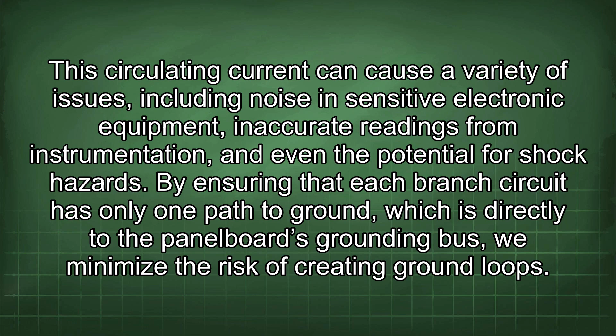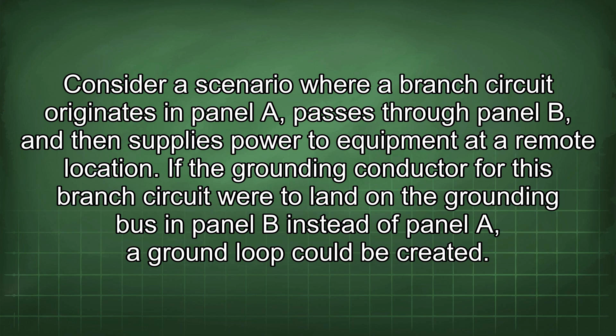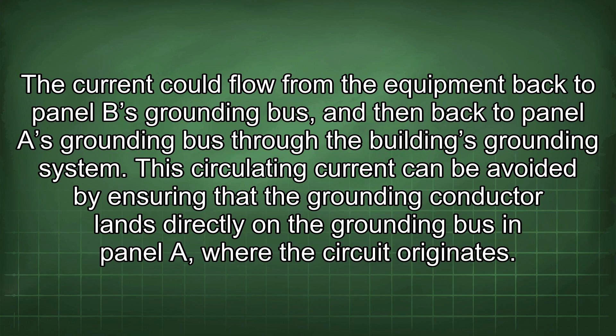Consider a scenario where a branch circuit originates in panel A, passes through panel B, and then supplies power to equipment at a remote location. If the grounding conductor for this branch circuit were to land on the grounding bus in panel B instead of panel A, a ground loop could be created. The current could flow from the equipment back to panel B's grounding bus, and then back to panel A's grounding bus through the building's grounding system. This circulating current can be avoided by ensuring that the grounding conductor lands directly on the grounding bus in panel A, where the circuit originates.